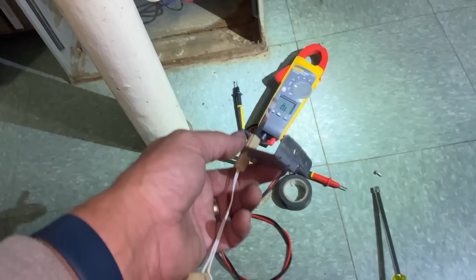No. But during maintenance of a heating appliance, we test the component and it should give you a certain reading, like I showed you on video. This was giving us nothing, an open line, because it's cracked, right? The same way I could test the pressure switch reads with certain equipment, and I could tell you if this is on its way out or not, if there's something wrong with it or not.